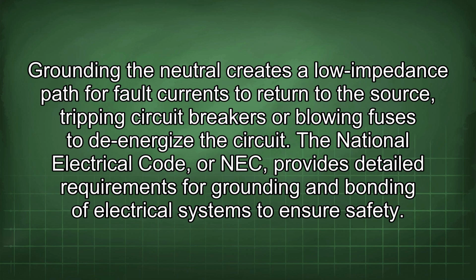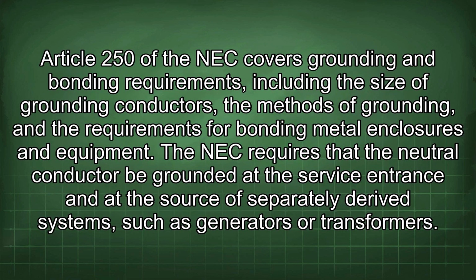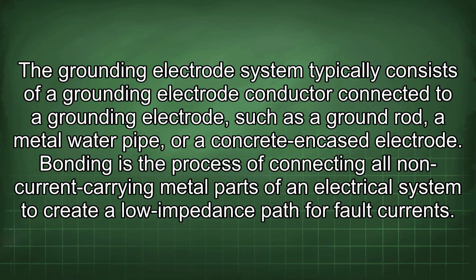The National Electrical Code, or NEC, provides detailed requirements for grounding and bonding of electrical systems to ensure safety. Article 250 of the NEC covers grounding and bonding requirements, including the size of grounding conductors, the methods of grounding, and the requirements for bonding metal enclosures and equipment. The NEC requires that the neutral conductor be grounded at the service entrance and at the source of separately derived systems such as generators or transformers. The grounding electrode system typically consists of a grounding electrode conductor connected to a grounding electrode, such as a ground rod, a metal water pipe, or a concrete encased electrode.